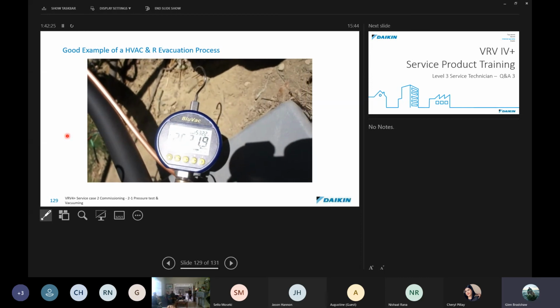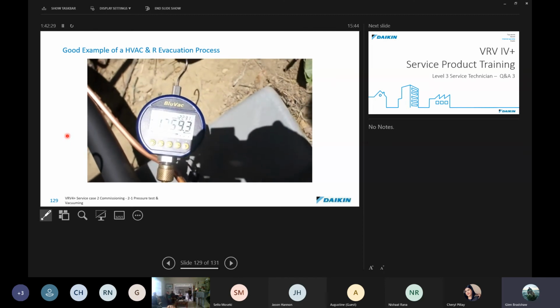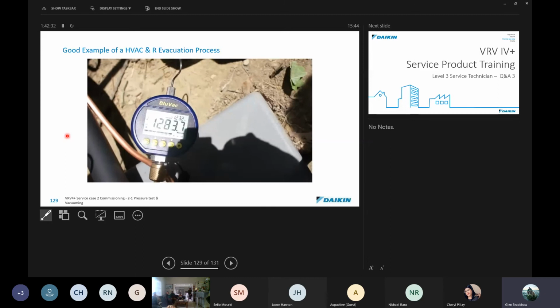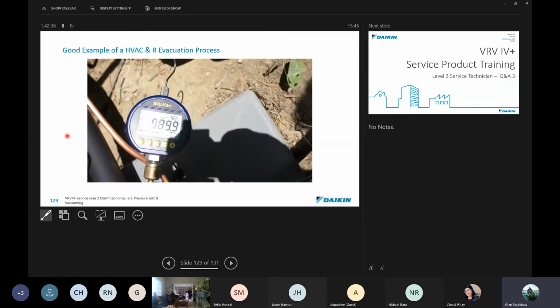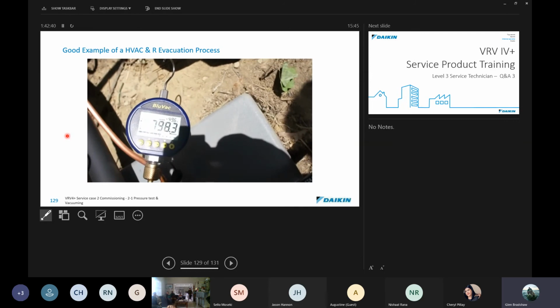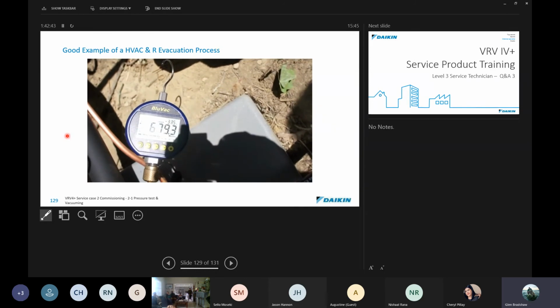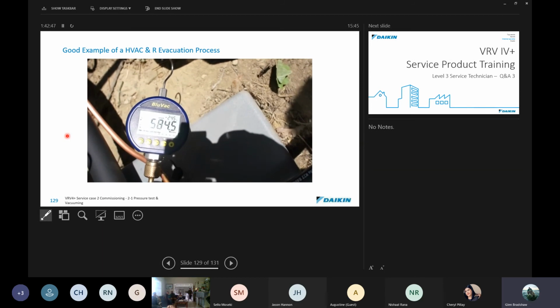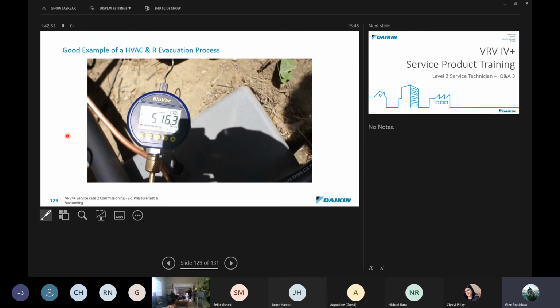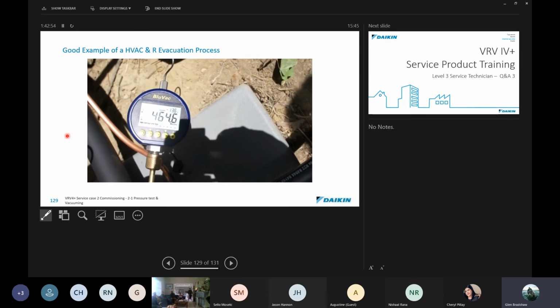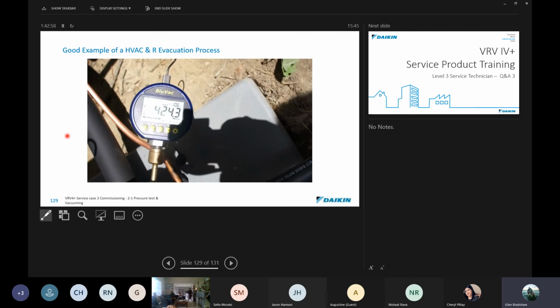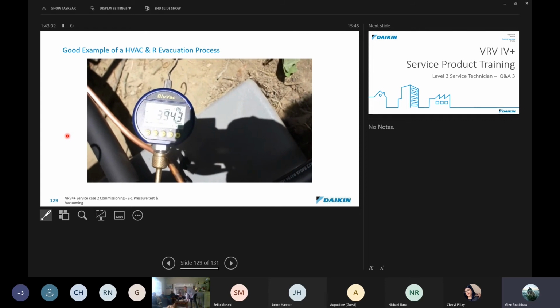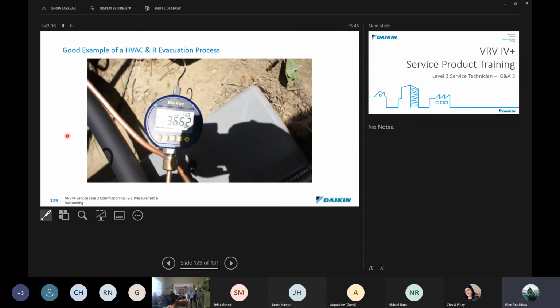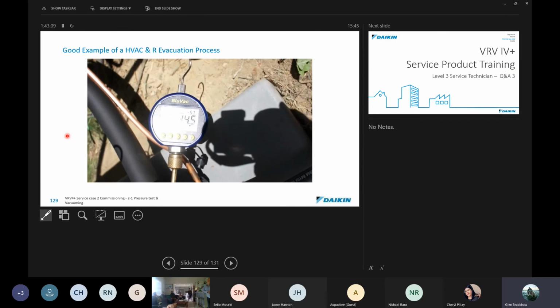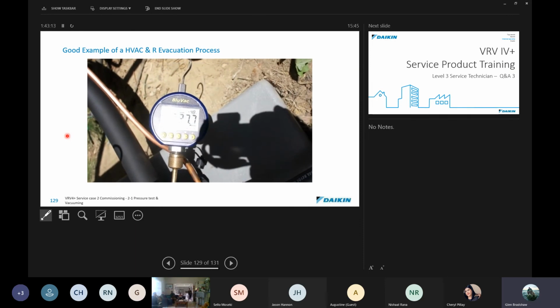3,000, 2,000, 900, 800, 700, 600, 500, 400, 300, 200. Now, obviously, as we get a deeper and deeper vacuum, it's going to go slower and slower.